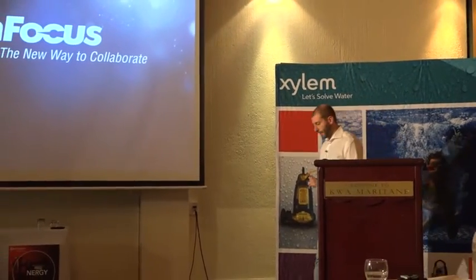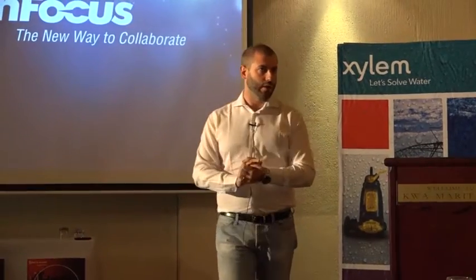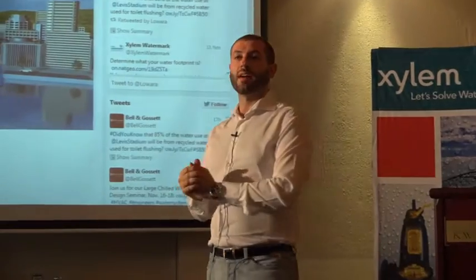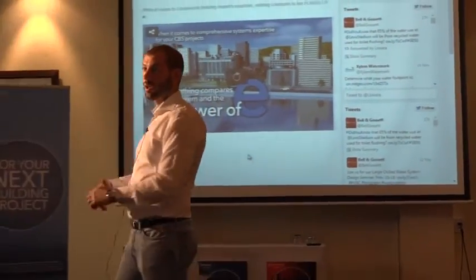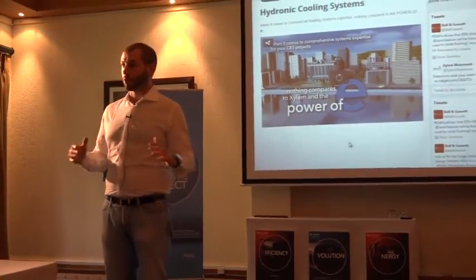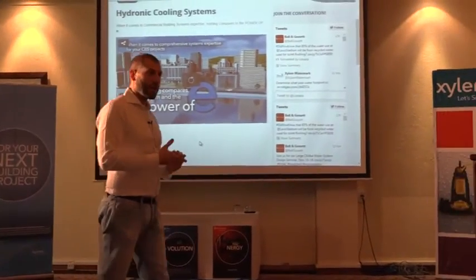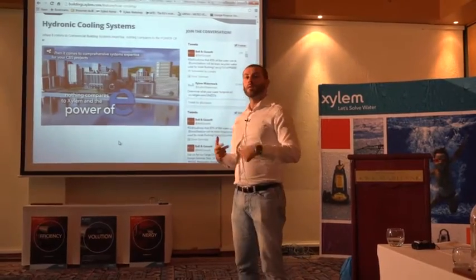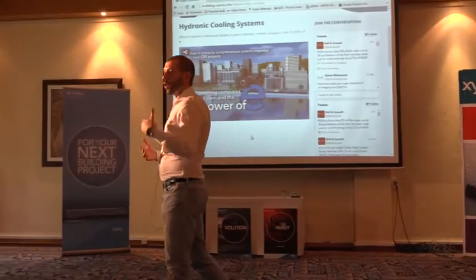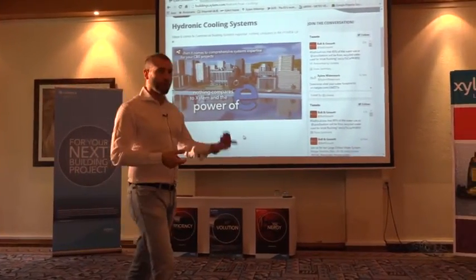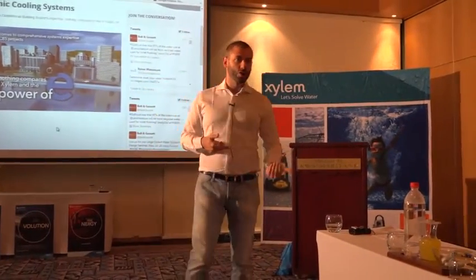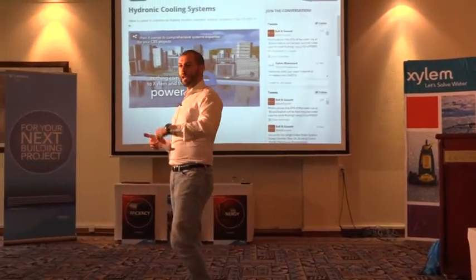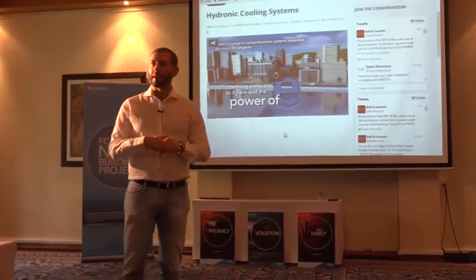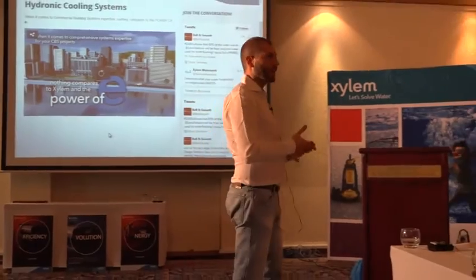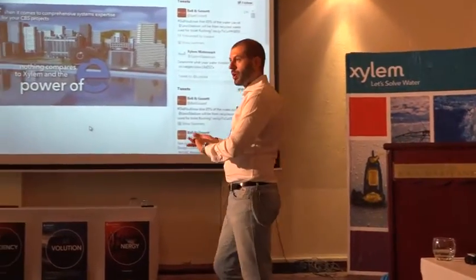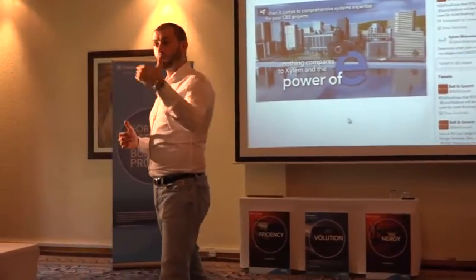As you saw, here there are a lot of variable frequency drivers. As we said on Thursday, a little bit squeezed because time was running. Variable frequency drivers are becoming common in the HVAC business. On the heating side, it's normal. So today, I would say 80% of the market requests come together with a variable frequency driver. The new generation of chiller systems all require a variable frequency driver, because the compressor is also working under a variable frequency driver. So the common control unit of the chiller needs an additional variable frequency driver for the pump, because there must be a balance between the compressor and the incoming flow. Okay? So I would say that for the cooling market too, it will become a standard.